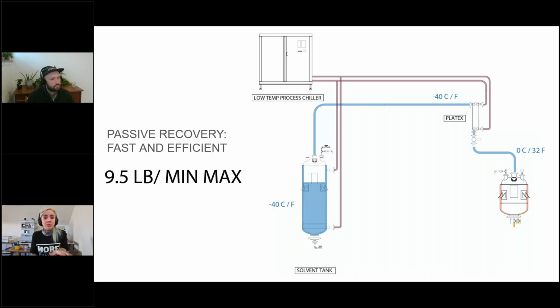And this is a problem for several reasons. The first being that there is almost no gas inside of that pump. Every time that it's pulling, you are getting just milligrams of material. And so you might hear that fast compressor, and it'll sound very busy, but it's getting nowhere. That's like a burnout with your tires. It sounds impressive, it's doing nothing. So that's slow recovery with a massive amount of energy. But because you're pulling vacuum, it also allows you to suck things out of that collection vessel that shouldn't come out. So you can aspirate, you can have misting, you can get stuff that isn't just your solvent, because you're not distilling if you don't have any positive pressure.